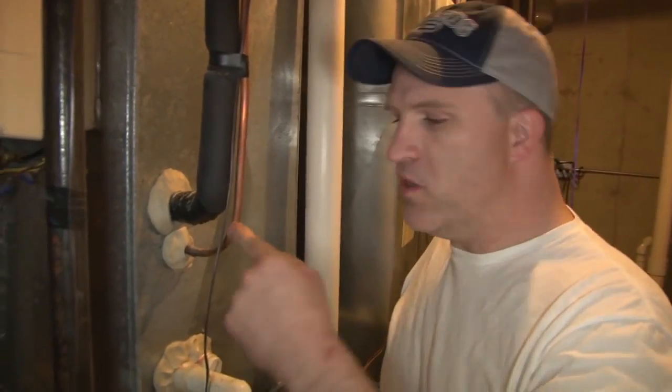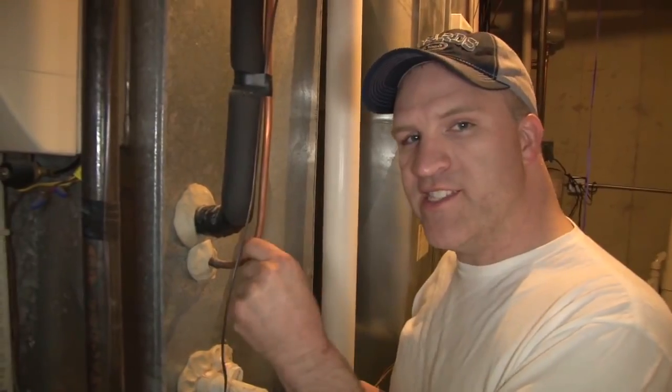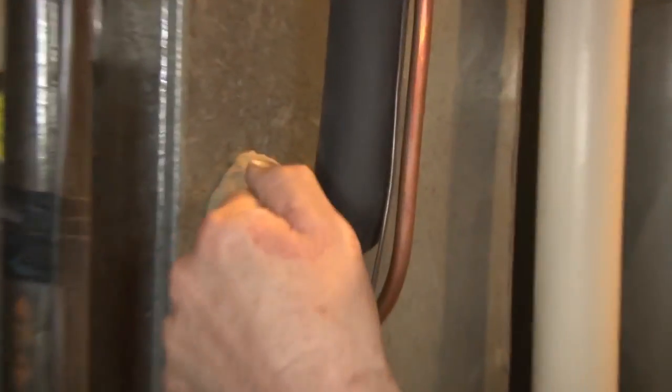If you come back to the coil and this liquid line right here is hissing or the suction line is freezing, then more than likely the unit's low on refrigerant. But that means that your compressor is working. If the unit's low on refrigerant, now is the time to call a technician. But at least you know that's the problem. If these two lines here are room temperature and there's no hissing noise, more than likely the compressor's off.